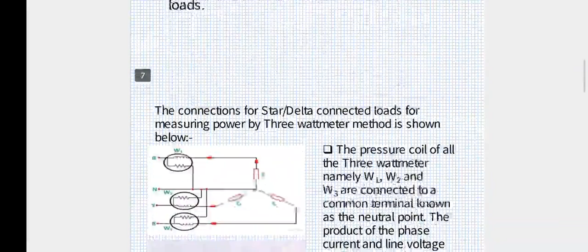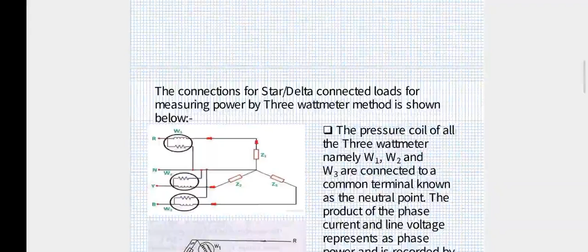The connections for star and delta connected loads for measuring the power by the 3 wattmeter method are shown below. You can see here the star connected load and the delta connected load. 3 wattmeters are connected, one in each line: wattmeter 1, wattmeter 2, and wattmeter 3. The pressure coils of all 3 wattmeters, namely W1, W2, and W3, are connected to a common terminal known as the neutral point. The product of phase current and phase voltage represents the phase power, and it is recorded by the individual wattmeter.